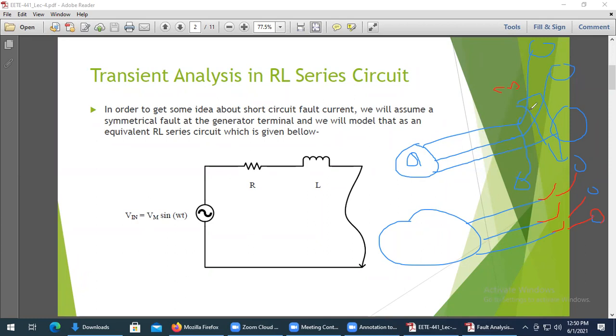So in this case, the symmetrical fault condition will trip all the circuit breakers, meaning you will not get power at any of the three terminals. You will get no power here, no power here, and no power here. But compare this to a fault occurring here, like a single phase to ground fault.